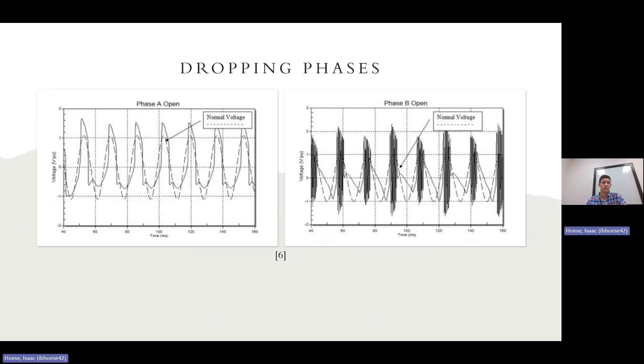And here's the dropping phases, the effects of that. So on the left side, we have phase A is open. And as you can see, it's about 1.5 per unit above, which is still a good amount. And when you open another phase, as you can see in the second graph, it goes all the way above two per unit. This is caused by the core being driven into saturation, and obviously the flux is not canceling out. So when one or two phases are open, it can create havoc on your system.